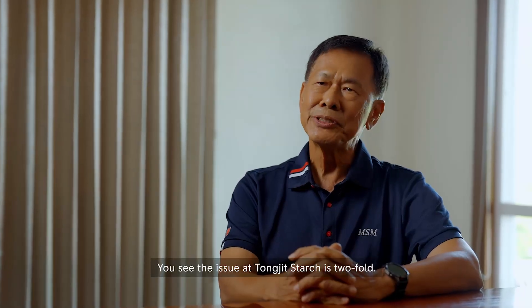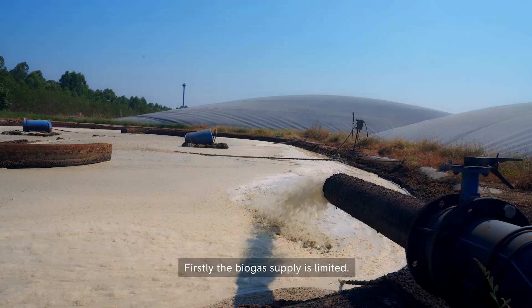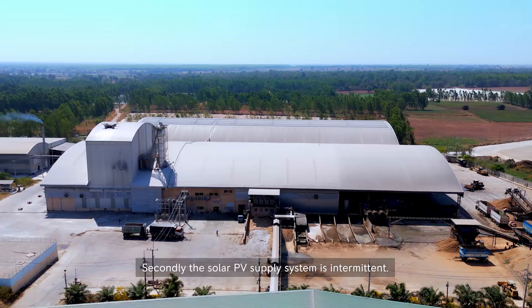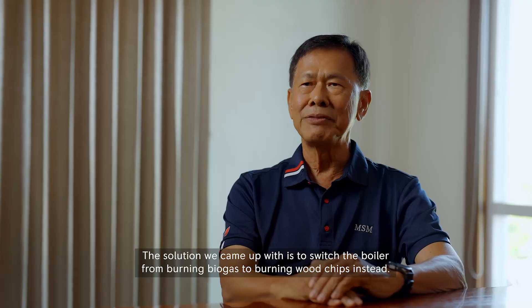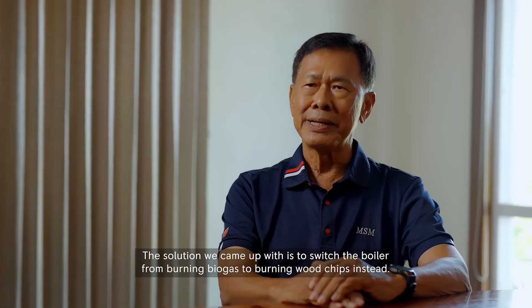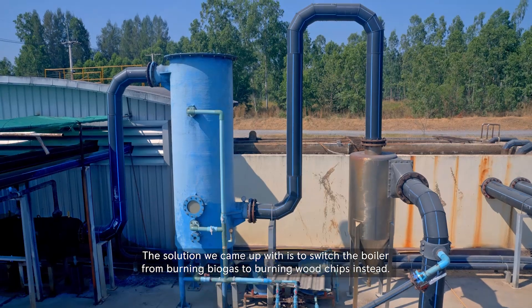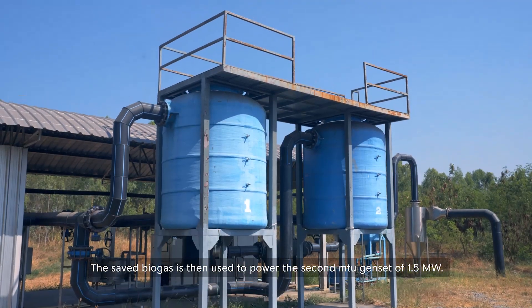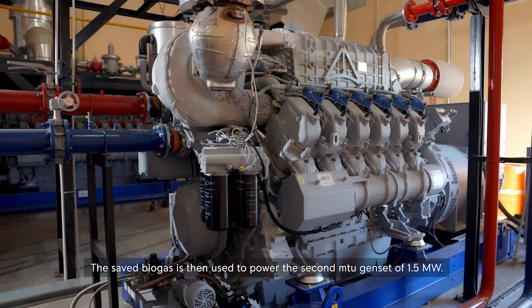The issues at Tongjit Starch are twofold: firstly, the biogas supply is limited; secondly, the solar PV supply system is intermittent. The solution was to switch the boiler from burning biogas to burning wood chips instead. The saved biogas is then used to power a second MTU genset of 1.5 MW.